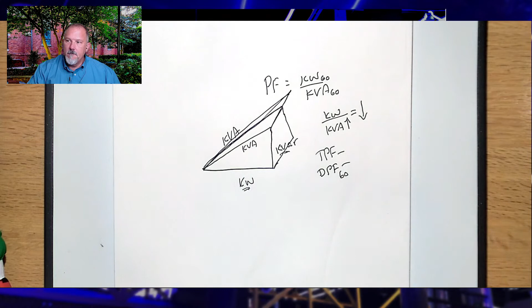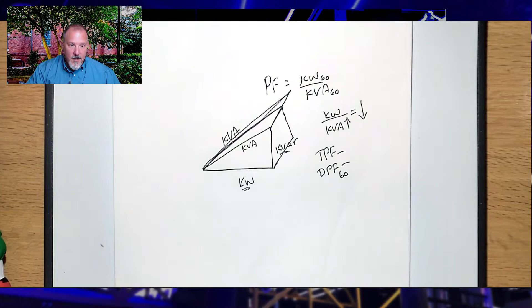Picture an industrial plant using 3 megawatts with no power factor penalty. Then I come in and install a new meter, and because you have harmonics from a bunch of drives, now you have a power factor penalty that you didn't have yesterday. People screamed about it, so the utility said, fine, we'll just bill you on displacement, 60 hertz.